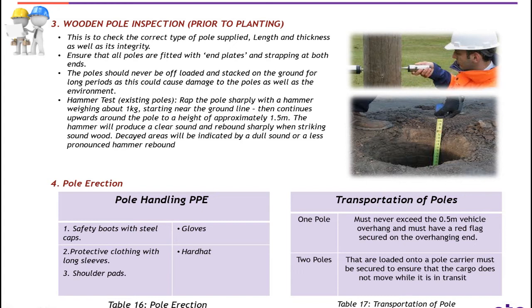Hammer test for existing poles. Rap the pole sharply with a hammer weighing about 1 kg, starting near the ground line then continuing around the pole to a height of approximately 1.5 m. The hammer will produce a clear sound and rebound sharply when striking sound wood. Decay areas will be indicated by a dull sound or a less pronounced hammer rebound.